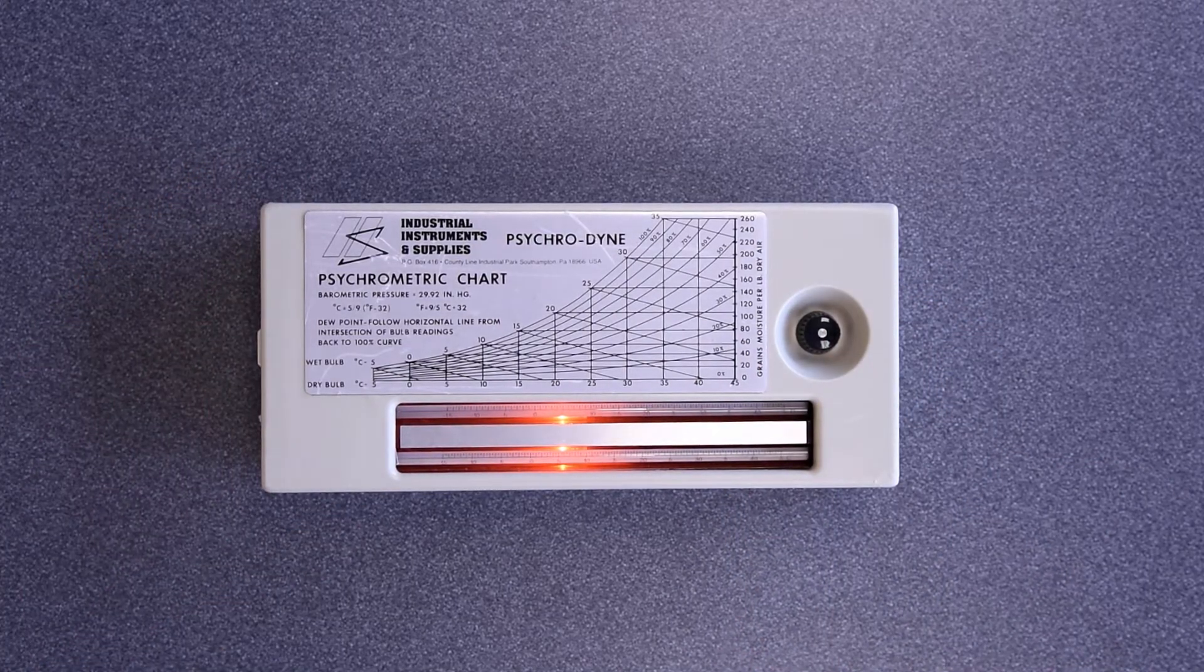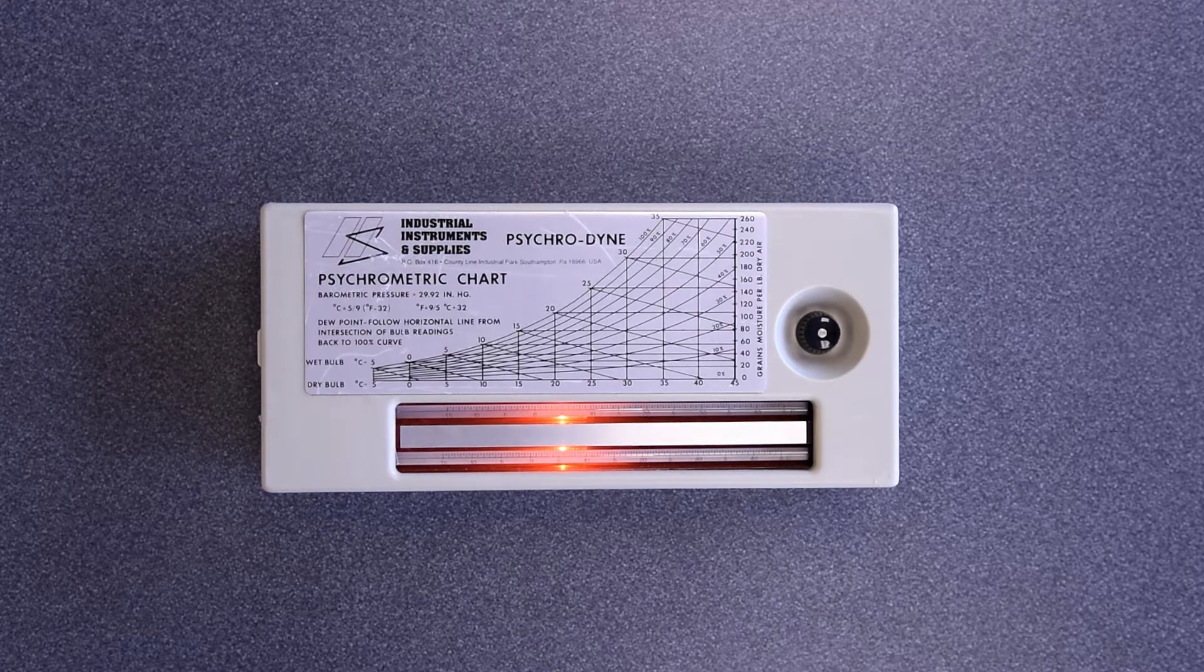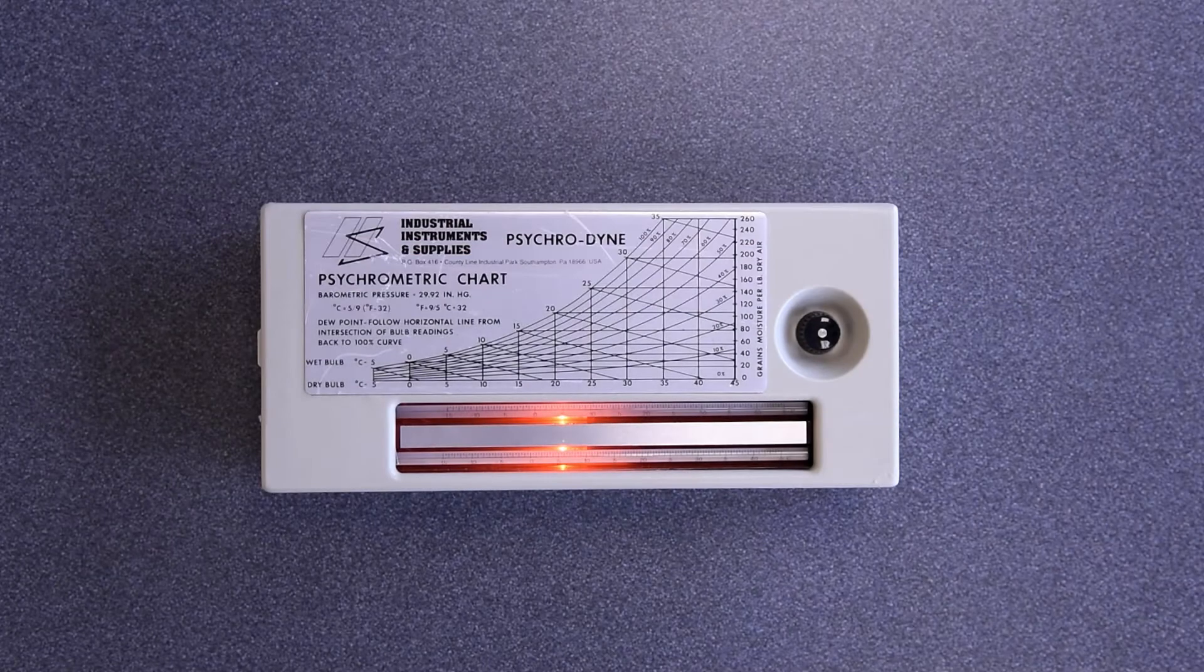As water evaporates from the wet sock, the wet bulb is cooled. You will see the temperature on the wet bulb thermometer dropping. The amount that the wet bulb is cooled depends on the amount of moisture in the air.